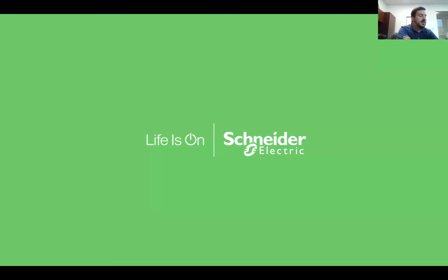Yeah, I can talk to it. So I think the question was alluding to the difference in when should I use a UPS versus a battery energy storage system. And it's really about duration. UPSs are really intended to be very short bursts of power, short duration, high power usually, basically to hold you over until a more traditional long-term standby source can come up, like a standby generator.